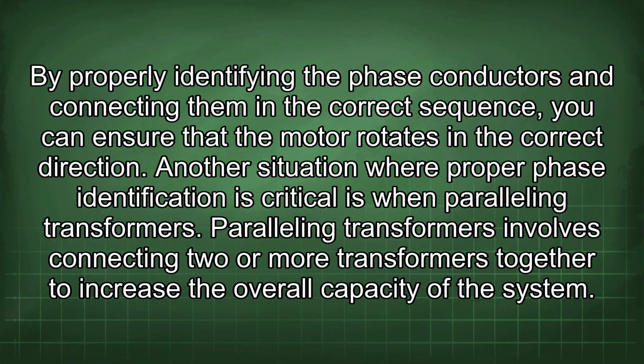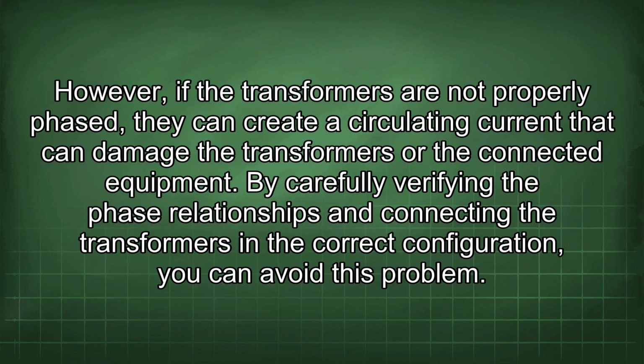Another situation where proper phase identification is critical is when paralleling transformers. Paralleling transformers involves connecting two or more transformers together to increase the overall capacity of the system. However, if the transformers are not properly phased, they can create a circulating current that can damage the transformers or the connected equipment. By carefully verifying the phase relationships and connecting the transformers in the correct configuration, you can avoid this problem.